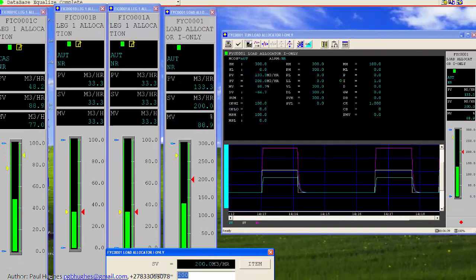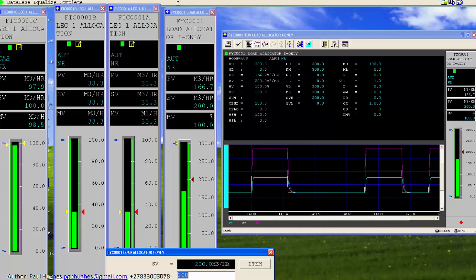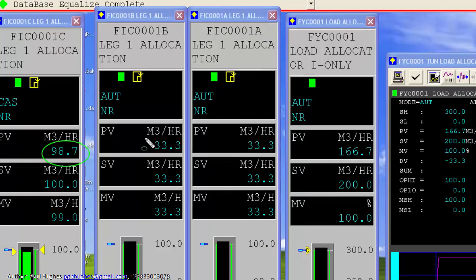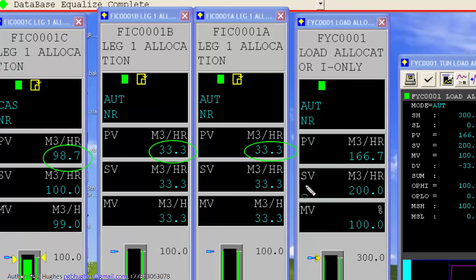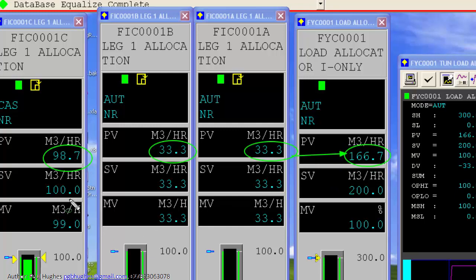With the master at saturation and output at 100%, the PV shows 98, and the individual slave set points are 33.3 and 33.3. Adding those up does not give 166.67 — because the total is the sum of the working set points: 100 plus 33.3 plus 33.3. This is important to note: you're summing the SVs, not the PVs, to get the PV of the load allocation controller.